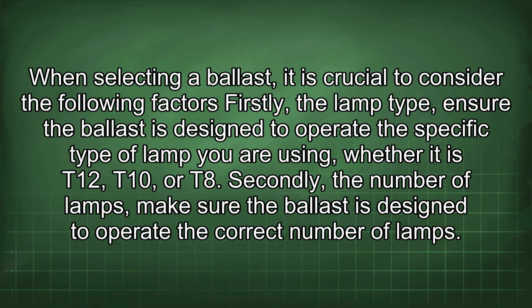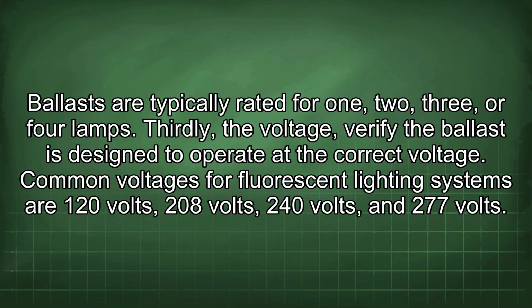When selecting a ballast, it is crucial to consider the following factors. Firstly, the lamp type. Ensure the ballast is designed to operate the specific type of lamp you are using, whether it is T12, T10, or T8. Secondly, the number of lamps. Make sure the ballast is designed to operate the correct number of lamps. Ballasts are typically rated for 1, 2, 3, or 4 lamps. Thirdly, the voltage. Verify the ballast is designed to operate at the correct voltage. Common voltages for fluorescent lighting systems are 120 volts, 208 volts, 240 volts, and 277 volts.